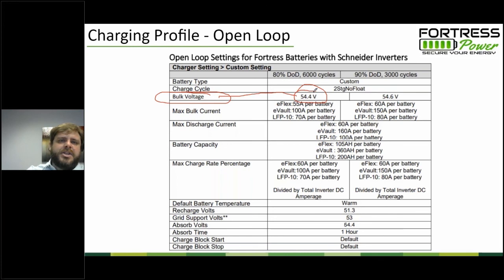When we do that strange equalization for resetting the BMS calibration, we're going to go at a little bit higher voltage than that. If we're doing closed loop communication, we'll be going at a little bit higher voltage as well. But for programming open loop, you're essentially programming all the voltage charges to be 54.4 volts. For that float charge, if you can't disable it, you put in 54.4 volts. Maybe try and look at the timing. For equalization, if you can't disable equalization, you're putting in 54.4 volts and then maybe setting the equalization time to 0.